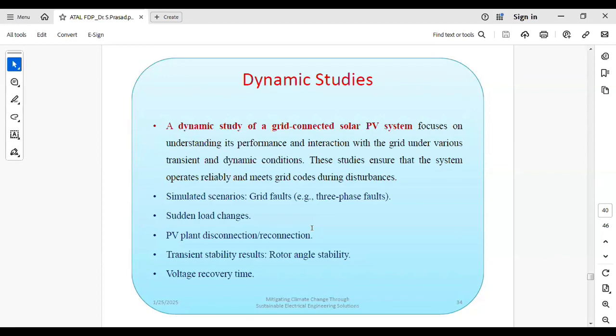Okay, so therefore we are conducting the LVRT and HVRT test, low voltage ride through and high voltage ride through. These are fault ride through tests, which come under the grid compliance study. Okay, so this is the grid impact study, and then the grid compliance study is there. That means you have to follow the CEA regulations. Okay, so that is the LVRT and HVRT test.